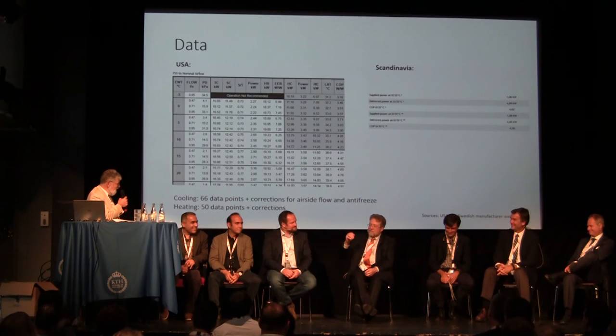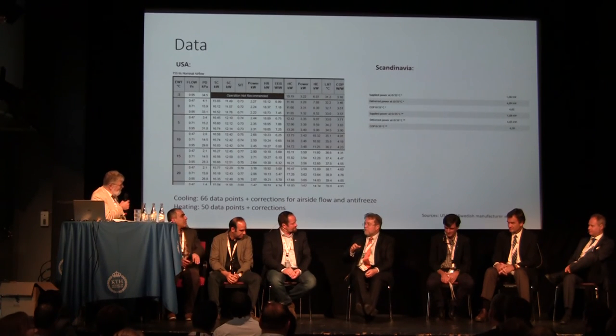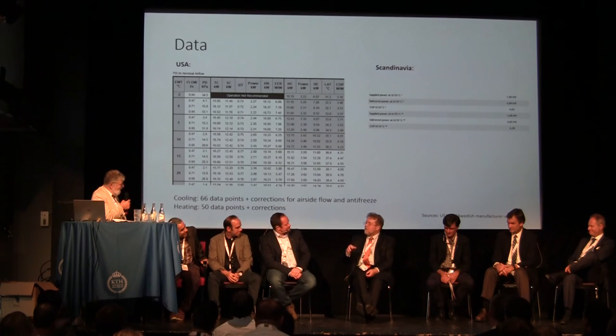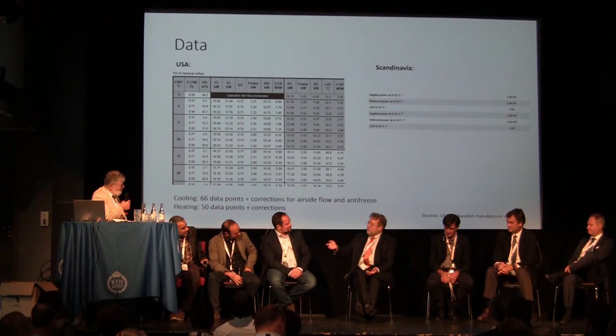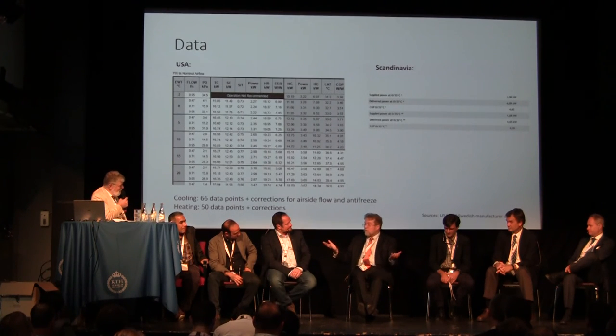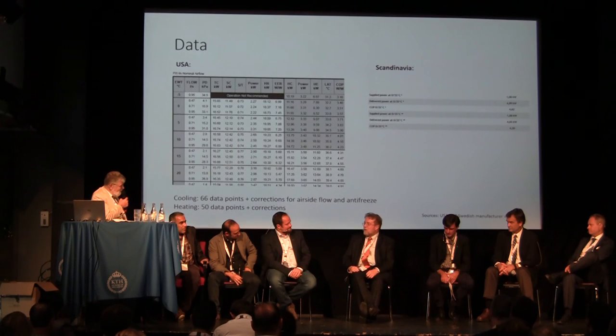When we talk about Memphis, it's not that different from Stillwater, Oklahoma — heating and cooling for a house are roughly balanced over the year. So I guess we'd have to call it the heat sink and source pump association. You do get much better cooling performance from a ground source heat pump than from a standard air conditioning unit. Those outside units aren't crap when installed, but after sitting in the weather for 10 years their performance degrades. The great benefit of ground source heat pumps in the US is that the equipment sits inside, out of the weather. We know of heat pumps from the 1970s that are still operational.